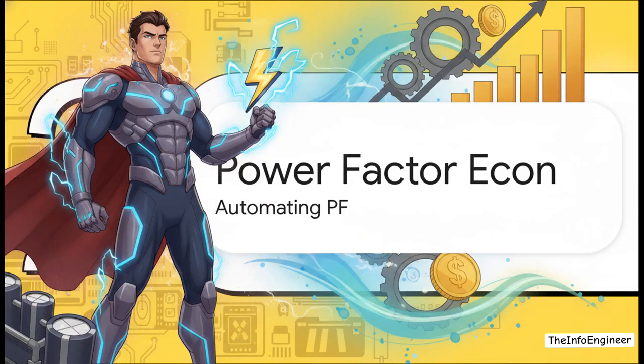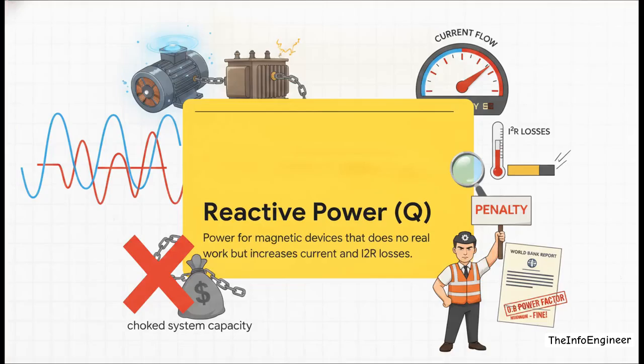Section 2. Power Factor Economics and Automating Reactive Power Compensation. Now, to really get the economics, you got to grasp the physics first. When inductive loads, like large motors or transformers, run, they cause your current to lag behind your voltage. This means your facility sucks down excess reactive power. It doesn't actually perform any real work, but it completely chokes your system capacity with higher current flow and I²R losses. And utilities absolutely hate this.